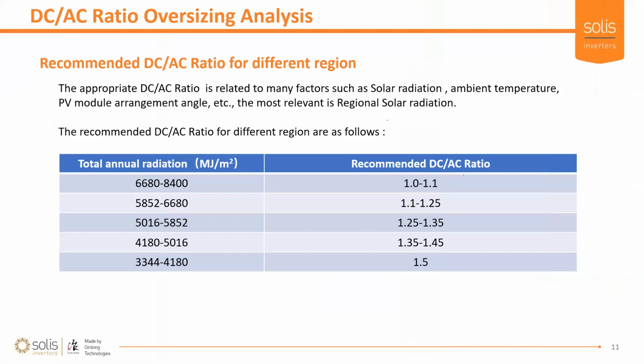Different regions obviously have different amounts of average radiation, and this helps us decide what is an acceptable level of overrating. I didn't mention this, but we do not allow you to just overrate to any ratio you like. You can't just put 6 kilowatt peak of panels on a 3 kilowatt inverter. That's an overrating of 2, and that's too much. In my mind anyway, maybe we can talk about it, but that sounds too much. The table shows us the ratios we allow. You need to check the annual radiation for the region the installation is going, and then check the table.